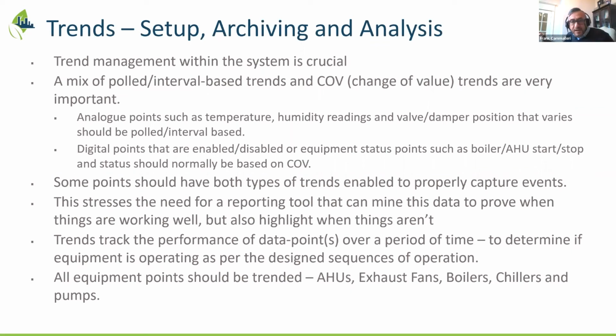So again, the types of trends - basically all key equipment points should be trended: air handling units, fans, boilers, chillers, and pumps. These days it's really important, but the big equipment especially - air handling units, boilers, and chillers - should be the priority. It's not that difficult once you demand it of your service provider or manufacturer when installing, to get them all set up, because they come in very handy after the fact.